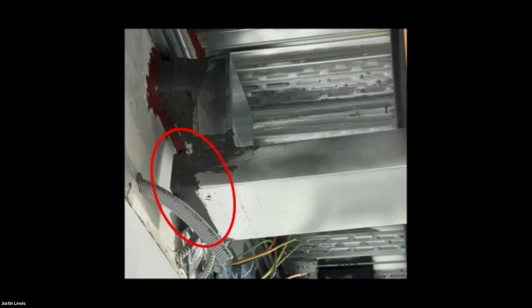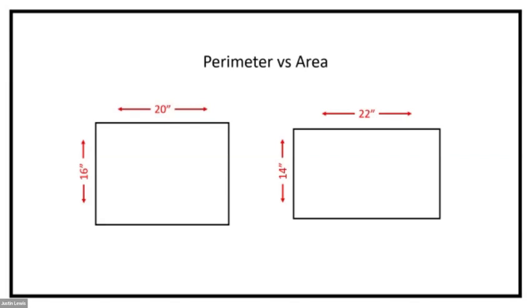Another issue that we run into is perimeter versus area. Now, with electrical lines, controls, sprinklers, and the myriad of other contractors who have work above the ceiling, it's often that we have less space than we thought we would. So what happens is a lot of times the installing contractor is supposed to put in a 16-inch high by 20-inch wide duct, but only a 14-inch high duct would fit. So they make the executive decision to take 2 inches off the height and add 2 inches to the width.